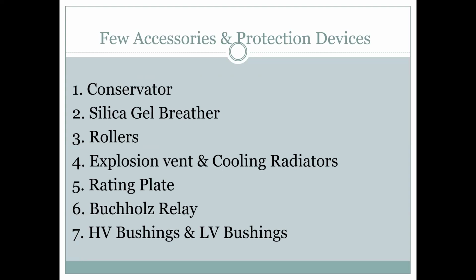Then these are the accessories we use: conservator, silica gel breather. When your transformer breathes, the outside air has moisture, so it goes to the silica gel, which absorbs the moisture, and dry air goes into the oil. So the oil does not get contaminated or moisturized. Then rollers, so you can move the transformer in any direction. You have the explosion vent, cooling radiators. These are the accessories normally given as per the IS standard, and accordingly the transformer manufacturer supplies them with the transformer. Any special requirement gets added to that.